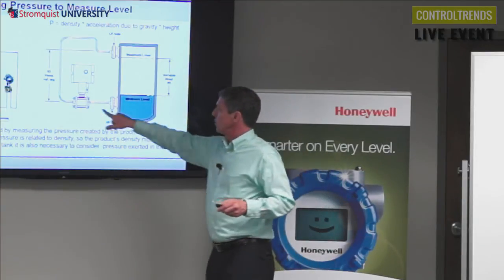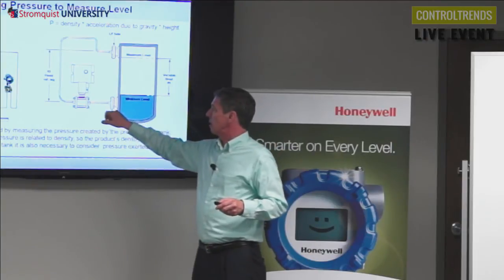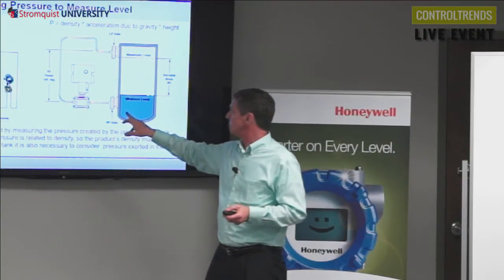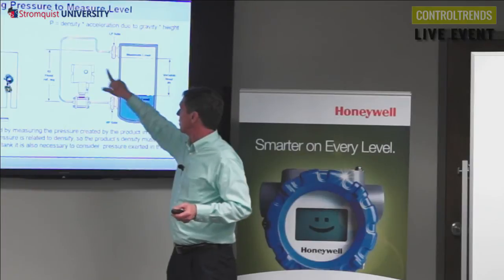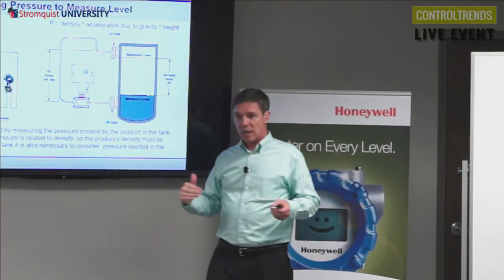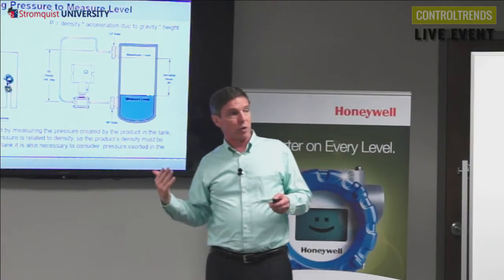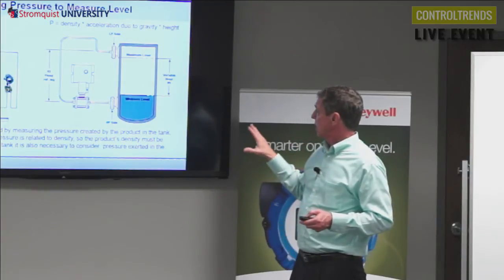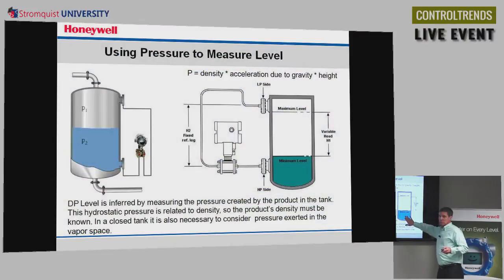Another way to do that is to use these capillaries. These are typically filled with a silicone oil and remote seals, measuring the high side and the low side. Same idea, as the level changes, the differential pressure changes.